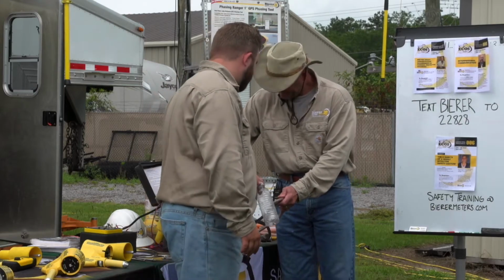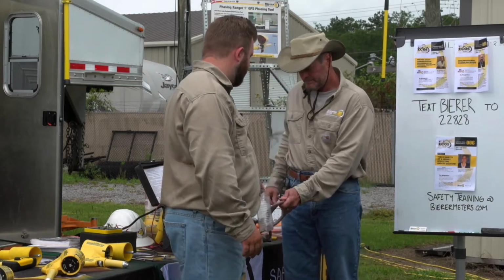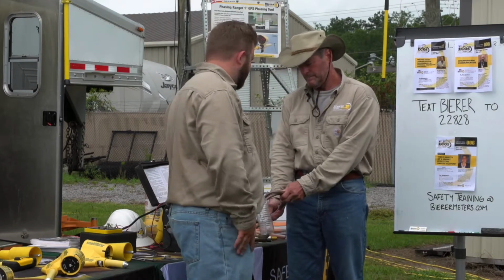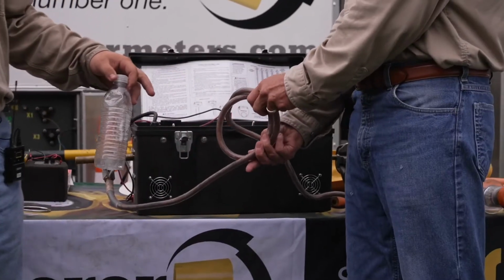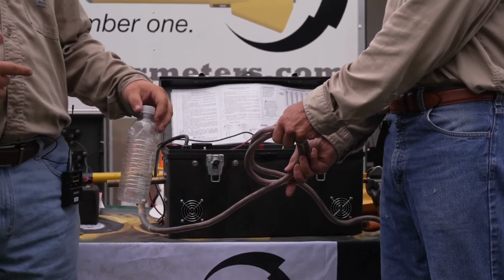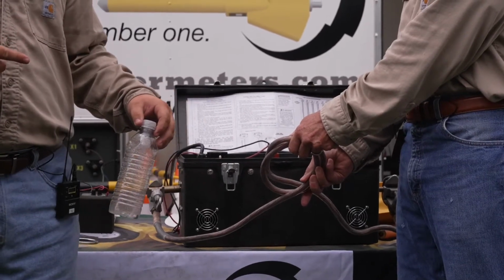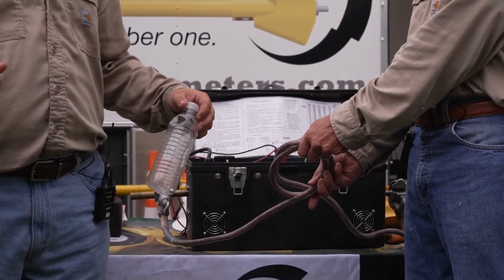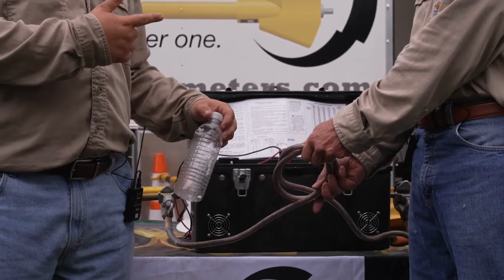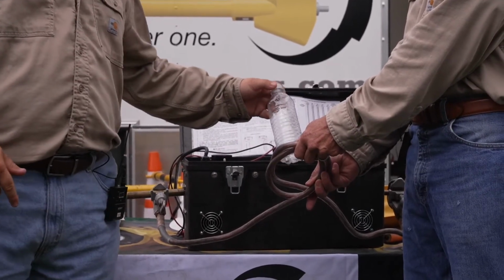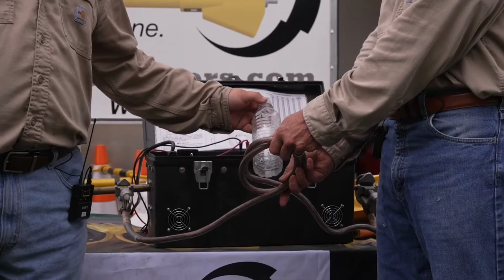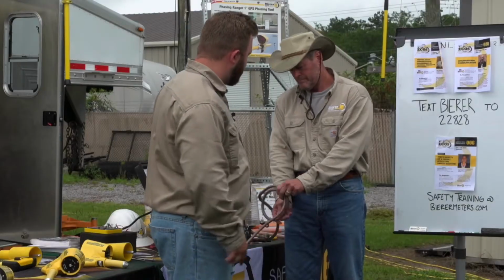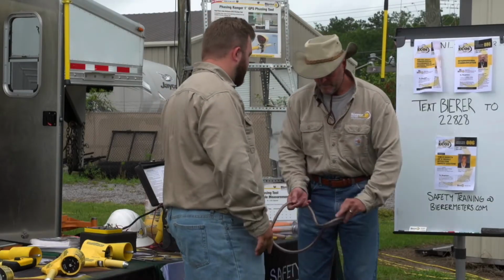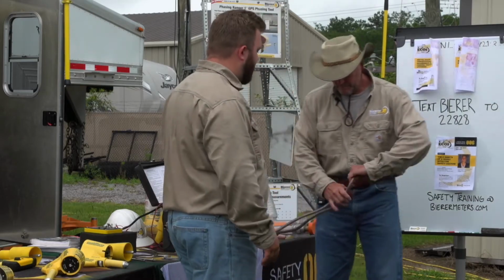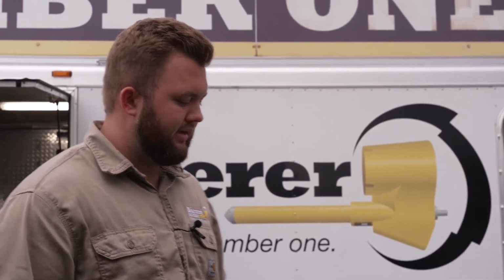In testing in tight parallel, instead of testing in tight parallel, we've got a loop configuration. This is to mimic how you don't want to use grounds out in the field. You don't want them in a loop configuration, you want them in as straight a line as possible, again to offset that magnetic field like Brent was talking about. Here's an example. There's that magnetic field that's going to cause resistance, and it's also going to cause a lot of unwanted activity if the ground becomes energized incidentally.